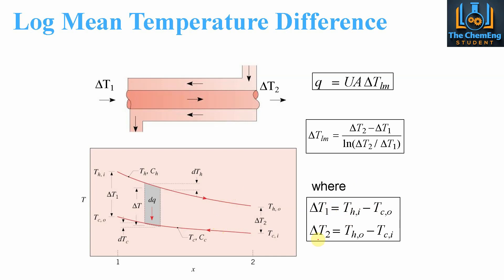For counter current flow, delta T1 is the inlet of the hot minus the outlet of the cold, and delta T2 is the outlet of the hot minus the inlet of the cold. This overall gives us a better log mean temperature difference compared to co-current flow. When you are given a problem and you know you don't have a uniform temperature difference through your heat exchanger, you must use the log mean temperature difference. You then need to determine whether you're dealing with counter current or co-current flow and adjust the delta T1 and delta T2 equations respectively.